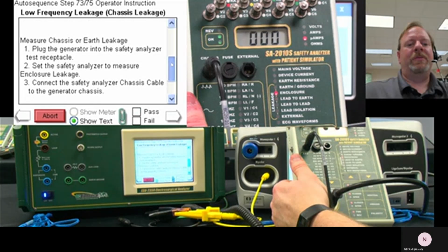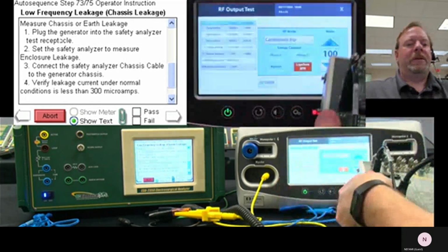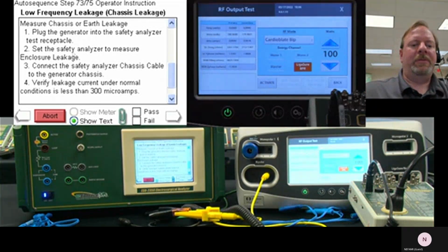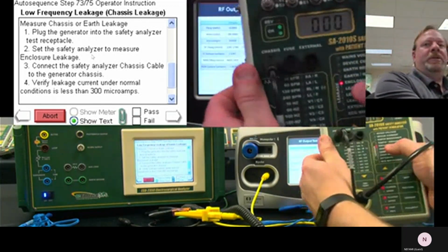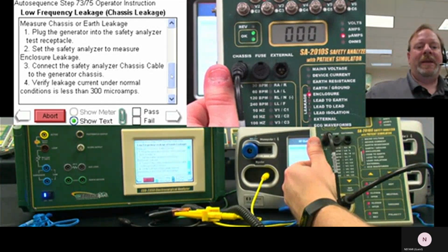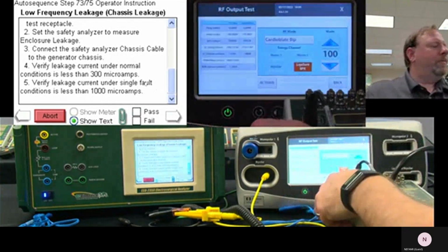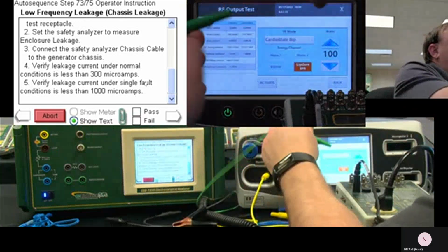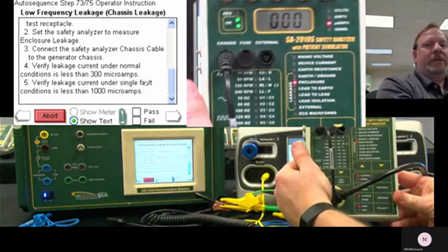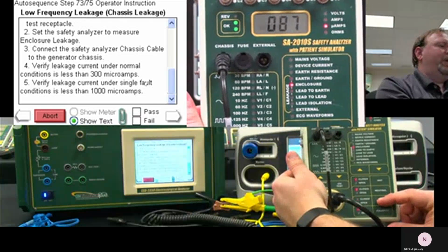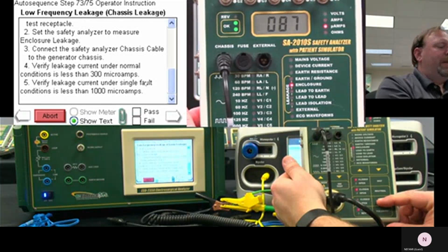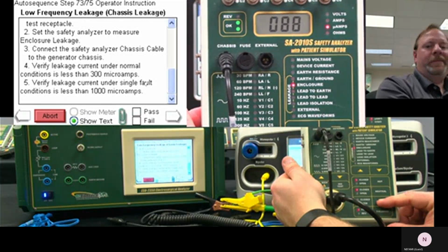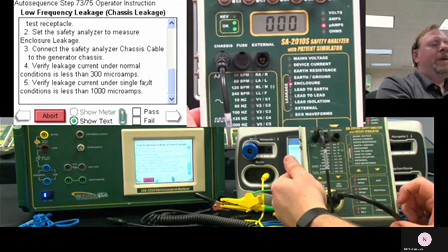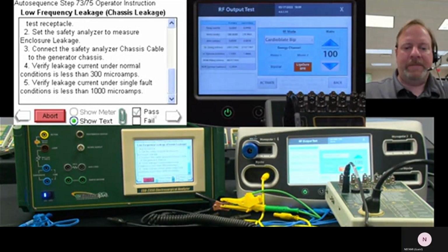So the chassis leakage. Measure the chassis earth leakage. Plug the generator into the receptacle, set the receptacle to measure enclosure leakage, which we still are. Connect the safety analyzer chassis cable to the generator chassis. What we had here is that green wire that went back to the chassis ground lug, enclosure. So connect that up. Normal conditions here. I create an abnormal condition. Oh, there we go, 88 microamps. So if ground gets open, that's how much current flows through the circuit. 88 is under 1,000, so we're still good. Okay, so I'll say, yep, you're good.